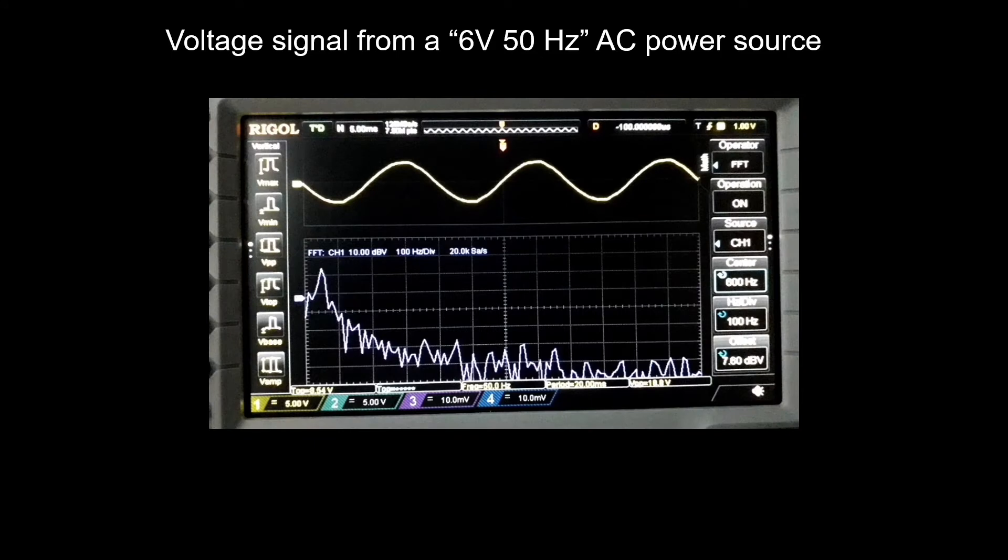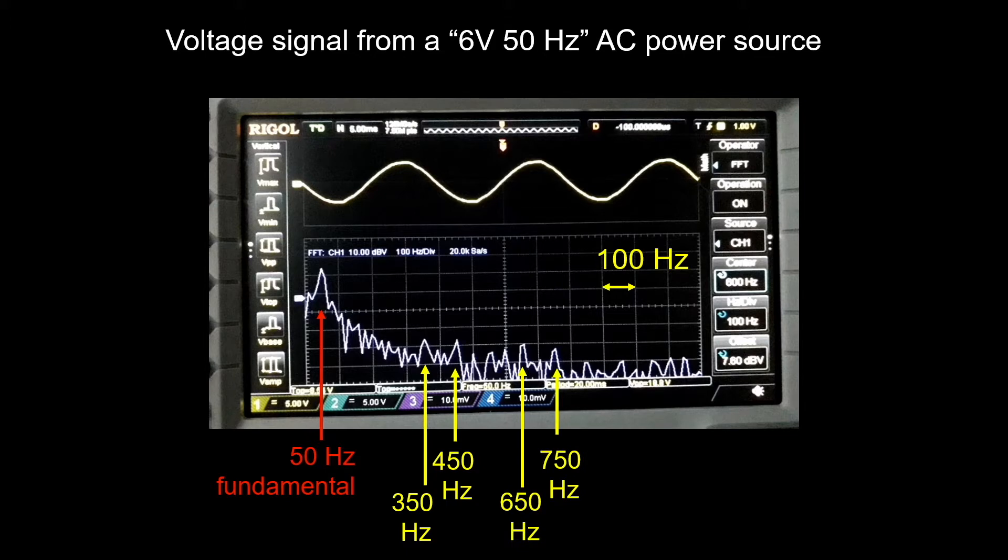After the Fourier transform we can see the frequencies inside the signal. The main peak at 50 Hertz corresponds to the fundamental frequency, but we can also see peaks at 350, 450, 650, and 750 Hertz. These correspond to the 7th, 9th, 13th, and 15th harmonics, so our power source already has some harmonics inside.